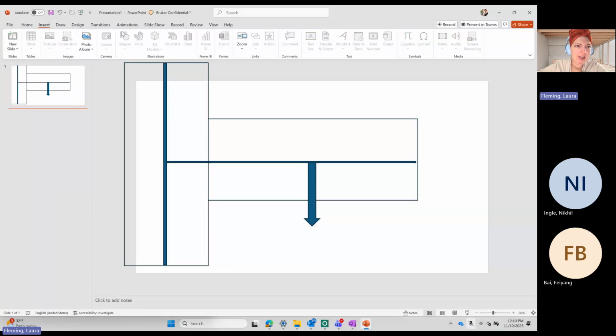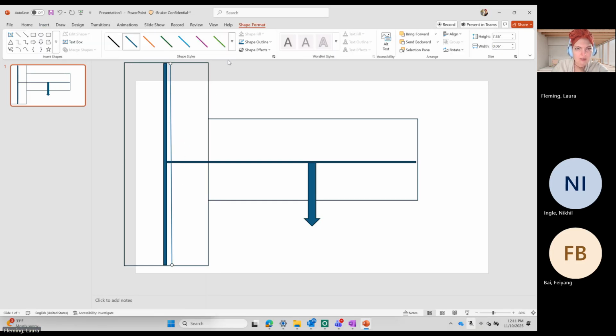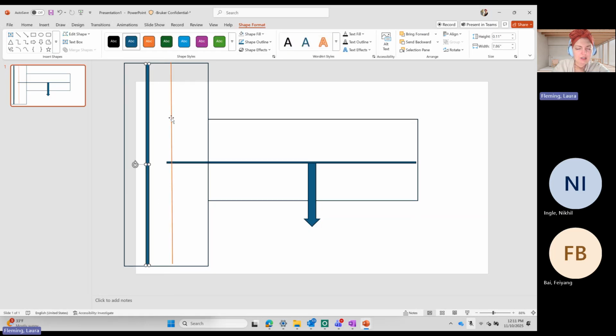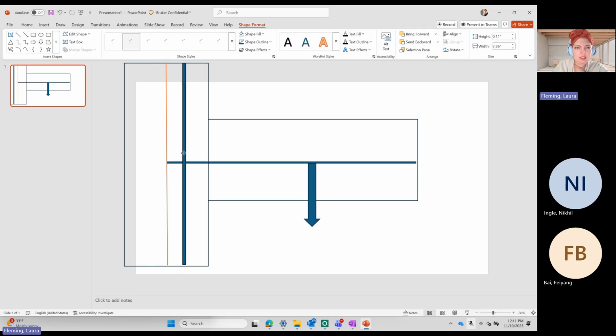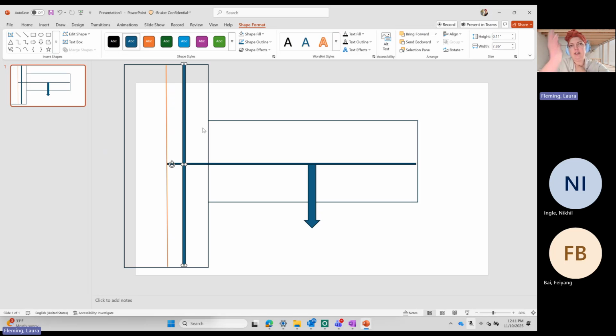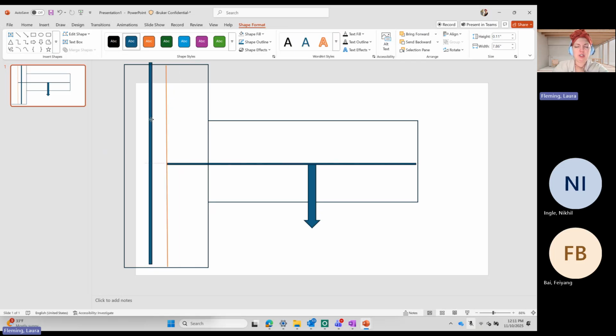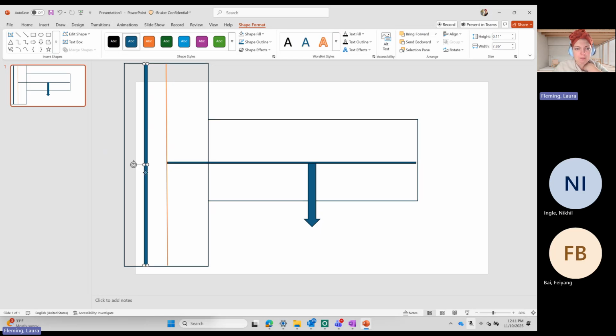Okay, so the thing is that we have this center line. So I'm just going to draw this here, make it orange. So this is like the center line of the transducer, where if our center plate is over here, it's under control of this plate, or if it's over here, it's under control of this plate. So basically, which side you're on is going to dictate which plate you calibrate to. And so you don't want to cross through this 0, 0 and switch control during a test because you're only calibrated to one. So for your purposes, you're over here at -10. And so that's your imaging position.